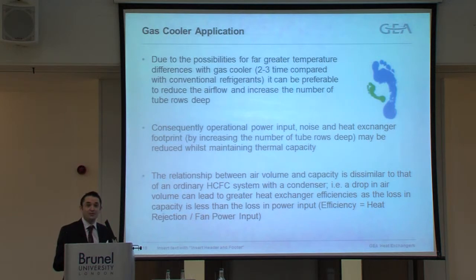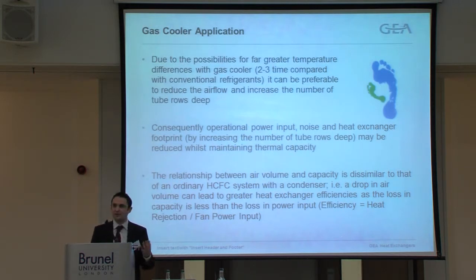Okay, so having now optimized the heat exchanger for the application, as described, we wanted to have a better understanding of the application and the operation. Now, due to the possibilities for far greater temperature differences within the gas cooler, which can be as much as 2 to 3 times that of a conventional refrigerant, it can be preferable to reduce the airflow and increase the number of tube rows deep. So for a conventional condenser, perhaps where you've got 3 fans deep, so you've got higher cost in the fans, more surface, more energy in the production of the gas cooler, we can reduce that down to possibly 1 fan with 6 tube rows deep.